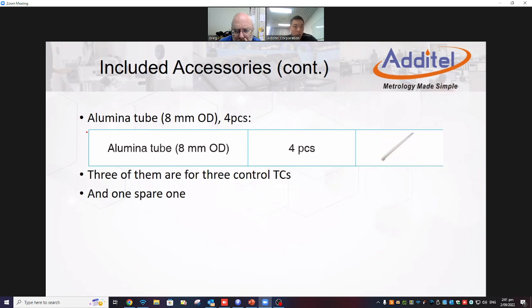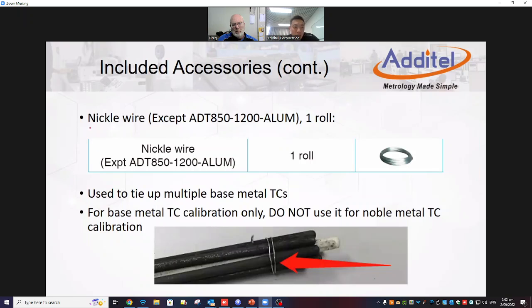So for the alumina tube, we have 8 millimeter outer diameter. We have 4 pieces. This is for the 3 control probes. Yeah, we give you a spare one because the 850 is a pretty huge one, and all the accessories are put inside a long box. Also, considering that alumina is not a very strong material, the carrier may break one during transportation, so we give you one spare. And then the nickel wire, the material is nickel. This is for the base metal, to make the bundle for the testing. We give you one roll for that.